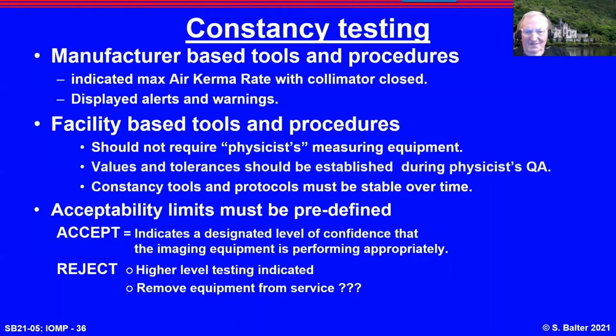Constancy testing. Manufacturers provide tools, and one new one, which I've just seen in a system we're installing right now: close the collimator, look at the indicated maximum air kerma rate. This is sort of neat, requires no tools. Manufacturers generally self-monitor the systems. If there's something the machine doesn't like, it will display an alert.